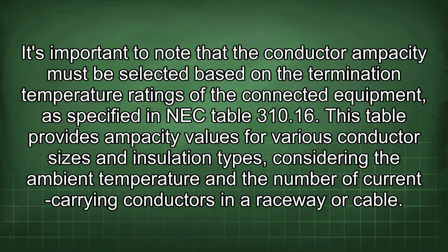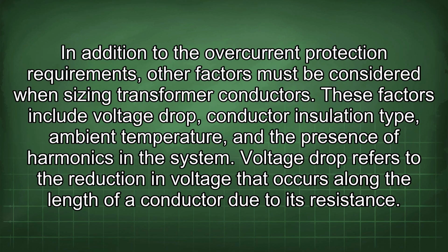It's important to note that the conductor ampacity must be selected based on the termination temperature ratings of the connected equipment, as specified in NEC Table 310.16. This table provides ampacity values for various conductor sizes and insulation types, considering the ambient temperature and the number of current-carrying conductors in a raceway or cable. In addition to the overcurrent protection requirements, other factors must be considered when sizing transformer conductors. These factors include voltage drop, conductor insulation type, ambient temperature, and the presence of harmonics in the system.